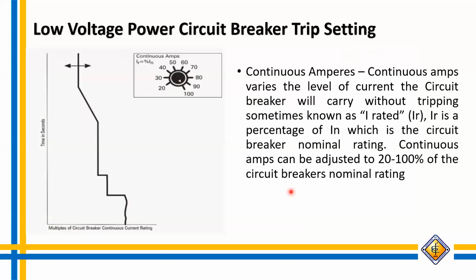We have the continuous amperes. Sorry. Okay. So continuous amperes varies the level of current the circuit breaker will carry without tripping. It can be adjusted to 20 to 100% of the circuit breaker nominal rating. For example, you have a 1000 ampere trip. It can be adjusted to 20% if the circuit you want to protect is around 200 amperes. So 20 to 100%, okay?